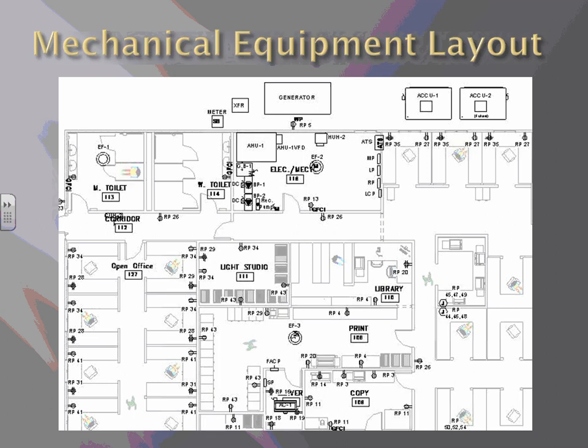And then I'm curious as to why you chose a closed transition automatic transfer switch. How did that impact you on your generator? We know they're more expensive. Open transition is typically cheaper. I decided to go with the closed transition because of a little bit shorter delay, you know, in the flicker of the lights between the transition. I guess that was so you're still using it for standby, you're not using it for load curtailment or peak shaving? Just standby.